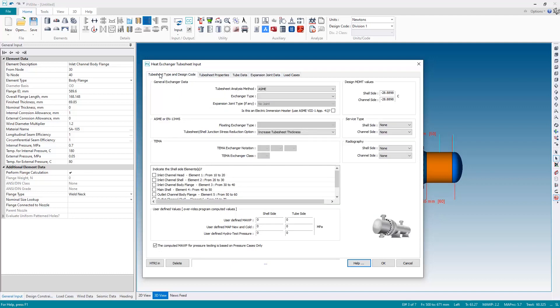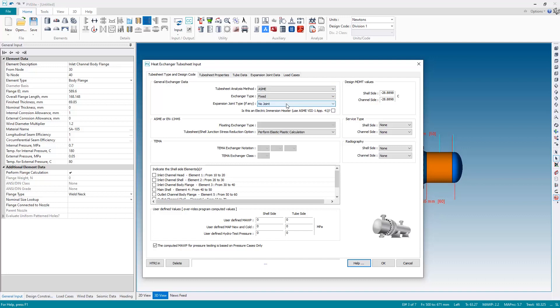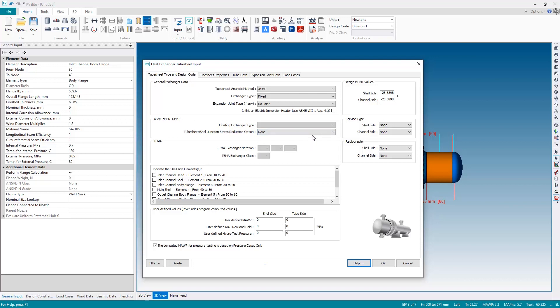Starting with the first one, let's pick the general information. So this will be an ASME tube sheet and this will be a fixed type heat exchanger, with no expansion joint. For the tube sheet and shell junction stress reduction option, we'll leave as is, or we'll set to none. If you remember in the previous video, you have to tell PVElite which are the shell side elements and which are the tube side elements. This is done in this listing area here, and you need to check the box for the shell side elements. This is really where giving everything a name becomes very useful. We have all the element names. If we didn't have the element names, we just have element one, element two with the node numbers. So giving things a name is very useful. Now, we only have one shell side element, which is the main shell. So we just need to check that check box and only that check box.